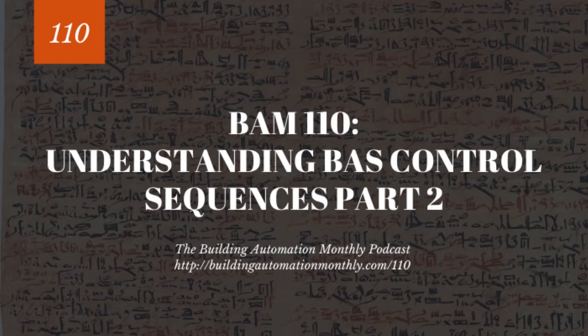Most times, what you're getting at the mixed air unit is 10 to 20% outdoor air damper. So 10 to 20% of that air volume being supplied to your space is actually outdoor air. The rest is mixed with return air from the space. So you're not getting a true 50 CFM. And I see this a lot in schools.